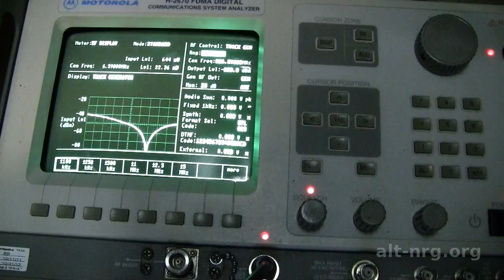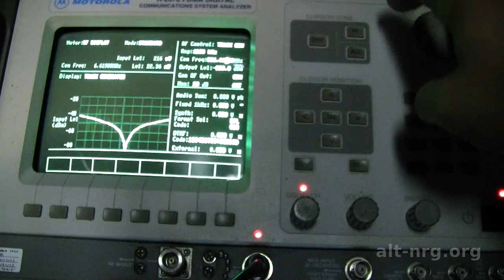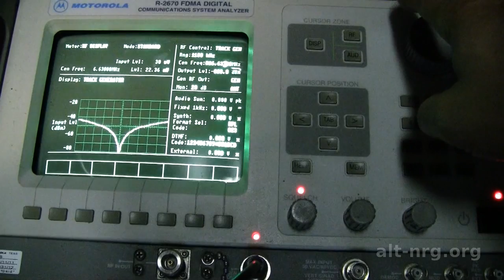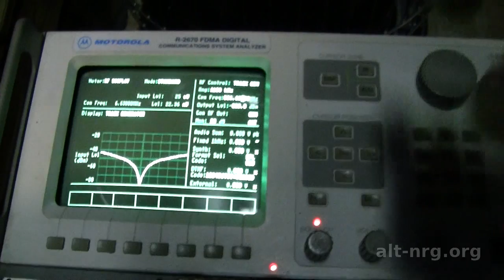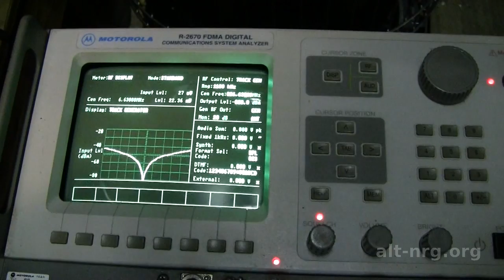To verify that, right now my range is at plus or minus 5 megahertz. I'm going to zero in to plus or minus 100 kilohertz so we can more clearly see exactly where the resonance peak is, and slowly increase my frequency. Right now I'm showing 6.614, 6.630 megahertz as the lowest natural resonant frequency for this particular coil and capacitance network.